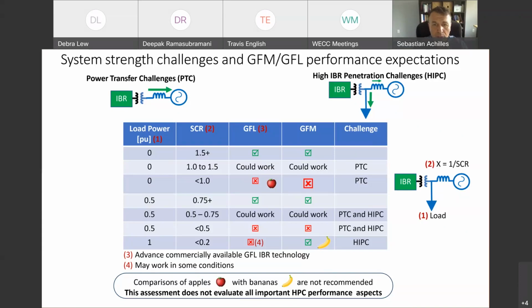And here, there are plenty of caution statements. On grid following, there is plenty of performance that can be expected. Different controls behave differently. So we're going to try to address that somehow, but any statement about whether something works or not can be questioned. It could be applicable for one control, but not to another. And the same thing applies to grid forming. There are some grid forming controls that behave differently than others. So it's hard to say that grid forming works for sure or doesn't work for sure. With that, let's look at the table.